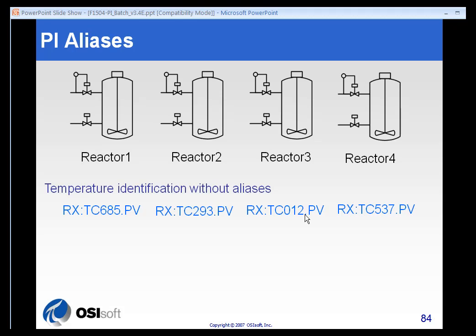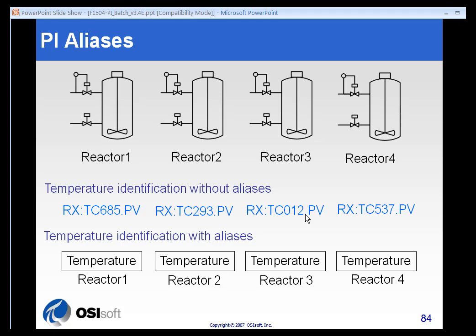That probably makes sense to someone in the process control group — the instrument technician or the process control engineer — it's probably very logical, but to everybody else, they don't know what that refers to. Figuring out what's happening in Reactor 3 can be very difficult. With aliasing in the Module Database, I simply create modules for each reactor, and in each module I can have a temperature alias. I can build reports and displays and query for data only knowing I need Reactor 3's temperature value — I don't have to know the tag name. It'll resolve it for me. That's essentially what the alias function of the Module Database does in the PI System.